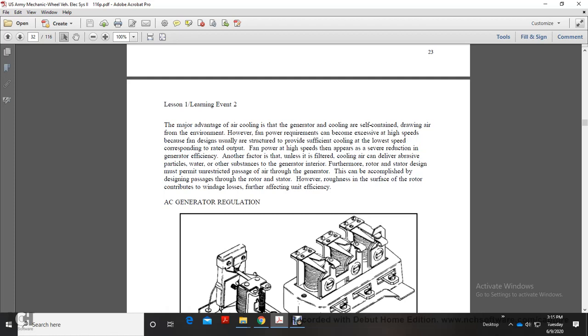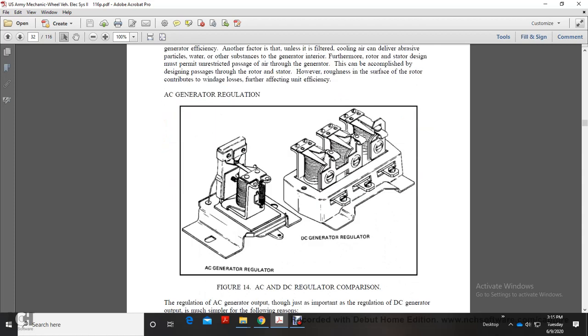Another factor is the life of the filter, since the cooling air can deliver abrasive particles, water and other substances into the generator interior. Furthermore, the rotor and stator design must permit unrestricted passage of the air through the generator. This can be accomplished by designing passages through the rotor and stator. The roughness of the surface of the rotor contributes to windage losses, further affecting unit efficiency.